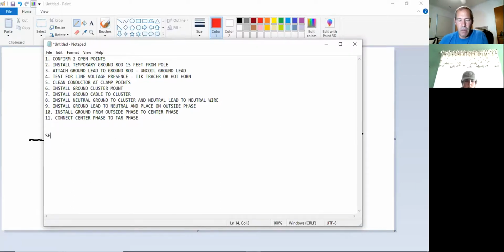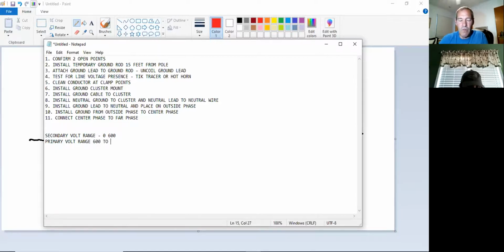Sorry about that. The secondary volt range. Wow, can't spell. Volt range. Does anybody remember what it was? 0 to what? 240. 600. Okay. What's the primary volt range? 7,200 or 12,470. The whole scope of all primaries. 600 to 34,500.